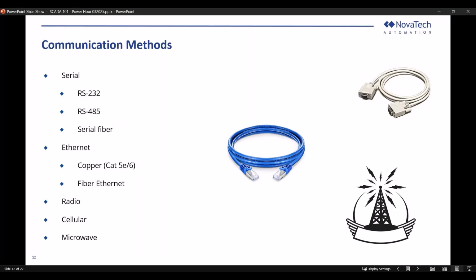Now we'll switch over to Ethernet. Ethernet is network communication, so anytime you put in an IP address, that's an Ethernet communication. The most common one you'll see at your substation is copper. That's your Cat5 and Cat6 cables with the RJ45 connectors. If you have a local network at home, that's what you're using as well. Copper tends to be about 10 megabit per second to 10 gigabit per second speed-wise, and distance-wise about 100 meters. Fiber, because of its ability to transmit, can do longer distances than copper, with faster speeds, up to 400 gigabit per second. Fiber is more expensive due to its greater bandwidth and reliability.